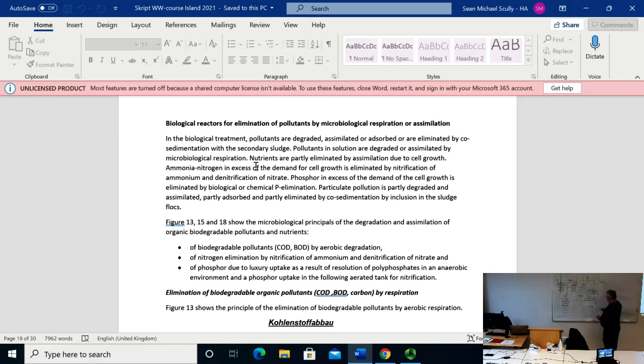Because this goes into the sludge treatment, and from the sludge treatment we have another filtrate here, 2 liters or 1.8 liter filtrate from sludge treatment, no? And in this sludge treatment, there's a little bit like 15% of nitrogen.